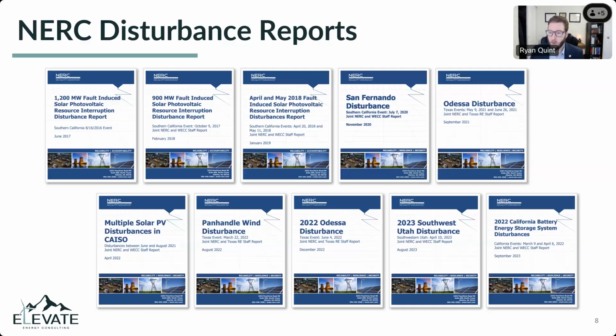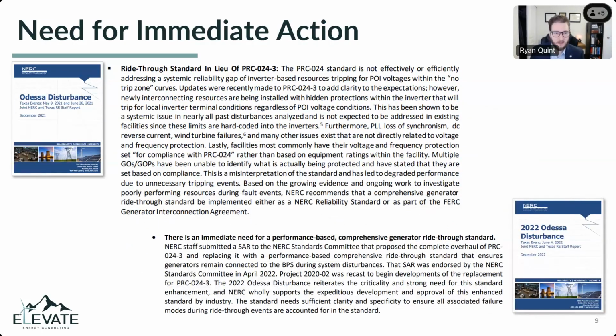Out of those reports came very strong recommendations from the ERO Enterprise to significantly enhance the ride-through standards, i.e. PRC-24, with a more performance-based comprehensive ride-through standard. PRC-24 has a long history, but ultimately resulted in a standard focused solely on voltage protection and frequency protection, and that's it. That is 1/100th of what a plant relies on to reliably ride through grid disturbances.